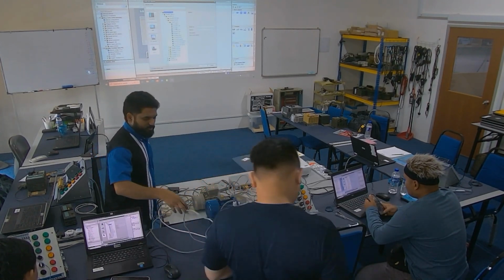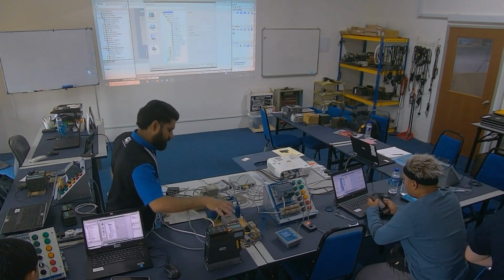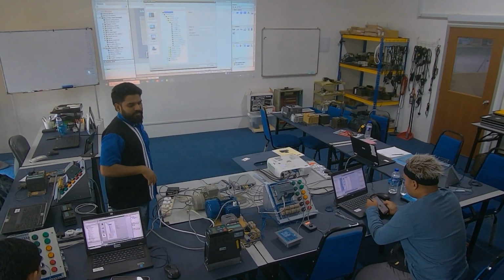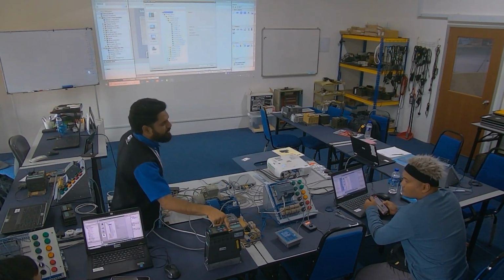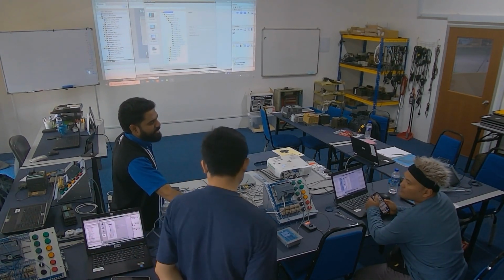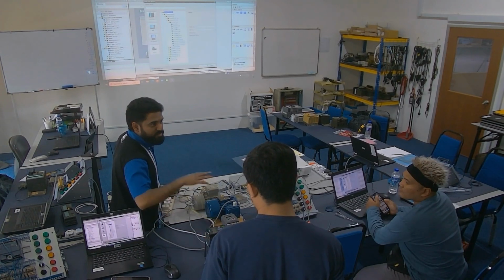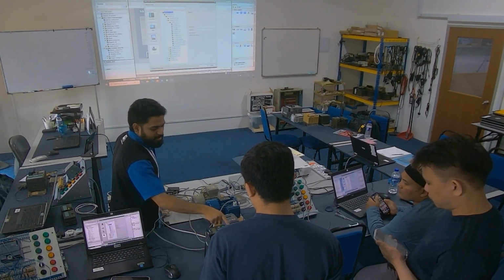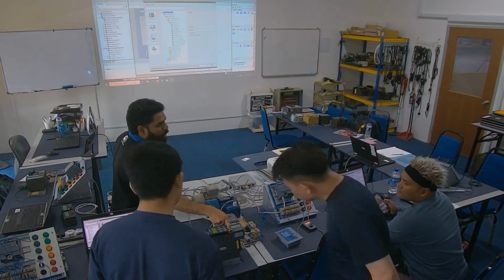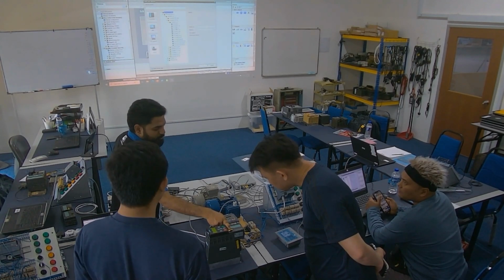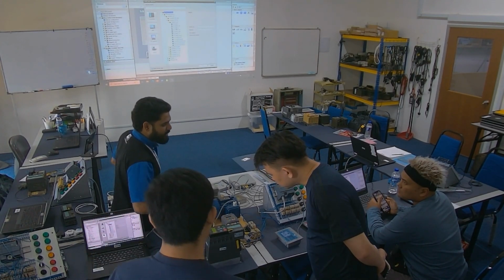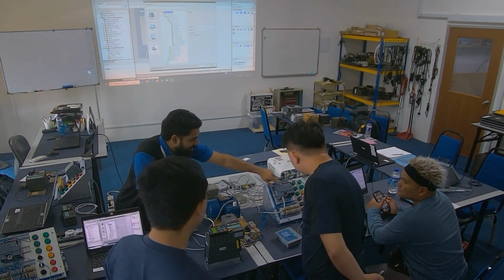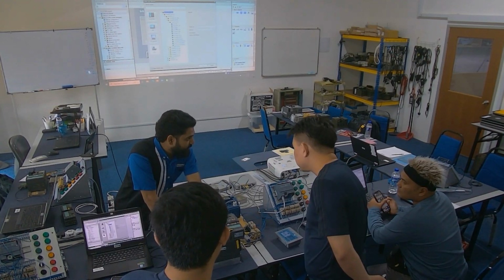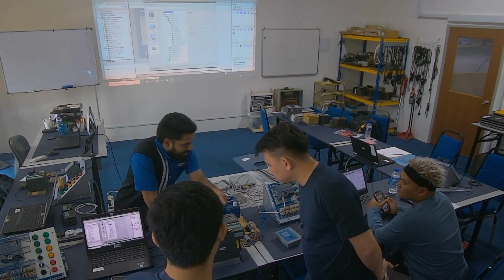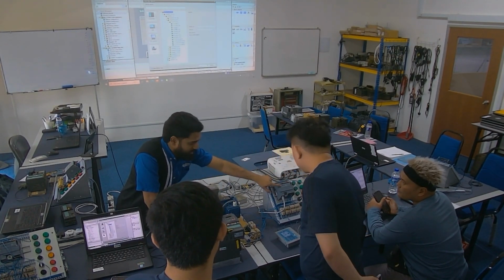Yes. Okay, now there's an error, right? Can you see bus fault? Yeah, actually inside here there's a program — the previous training I used this. Bus fault means communication error. Why the error? Because this PLC now doesn't have this drive inside here. The moment I add this drive into here, then it's an error.